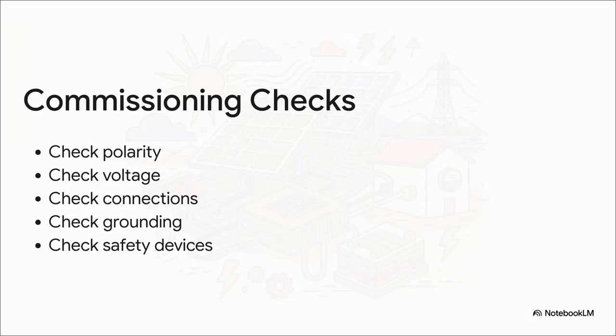But before we can experience that magic in real life, we have to test everything. You never just flip the switch and hope for the best. Our cartoon technician runs through a rigorous commissioning checklist. Using a digital meter, they meticulously check the polarity, verify all voltages are within range, inspect the physical connections, test the grounding for safety, and confirm every isolator and breaker is doing its job.